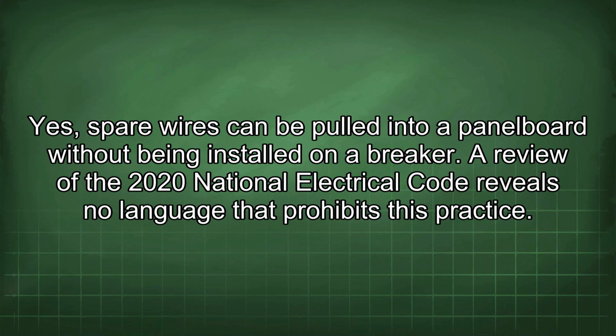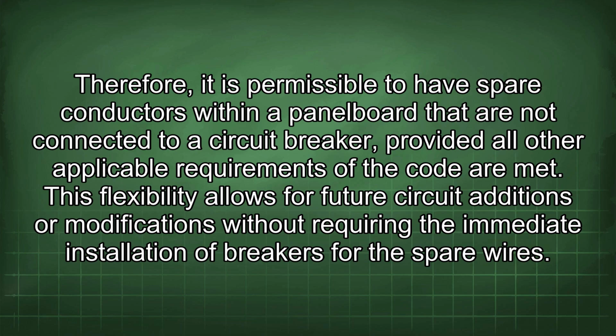Yes, spare wires can be pulled into a panel board without being installed on a breaker. A review of the 2020 National Electrical Code reveals no language that prohibits this practice. Therefore, it is permissible to have spare conductors within a panel board that are not connected to a circuit breaker, provided all other applicable requirements of the code are met.